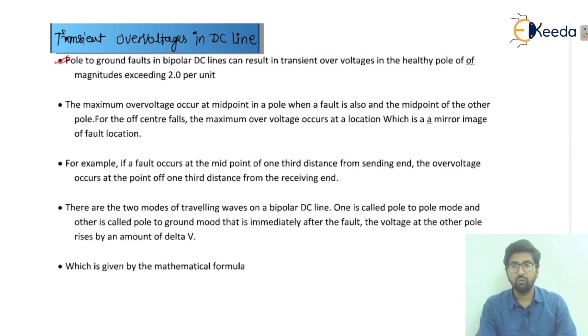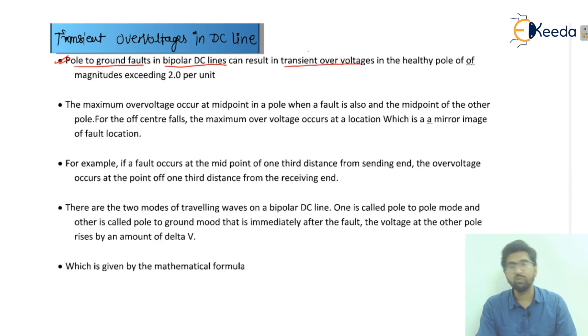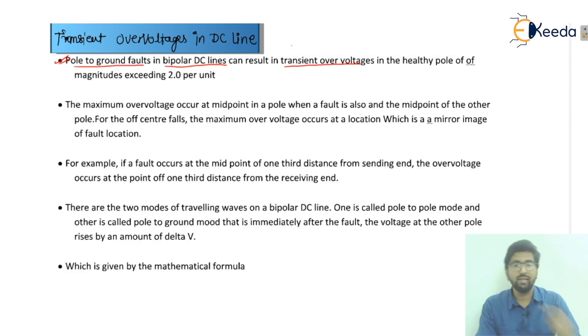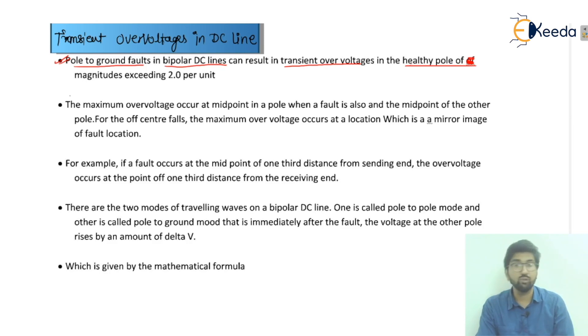If we talk about the pole-to-ground faults in the bipolar DC lines — we have DC lines as monopolar, bipolar, and homopolar — these can result in transient overvoltages. These transient overvoltages are of short duration and occur in the healthy pole. The magnitude of these transient overvoltages exceeds 2.0 per unit.